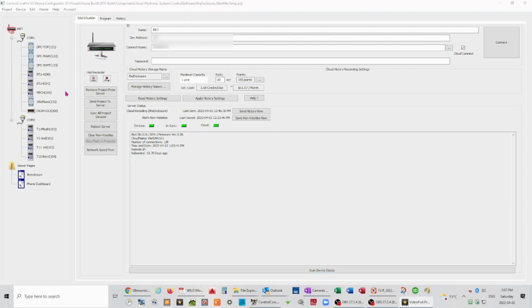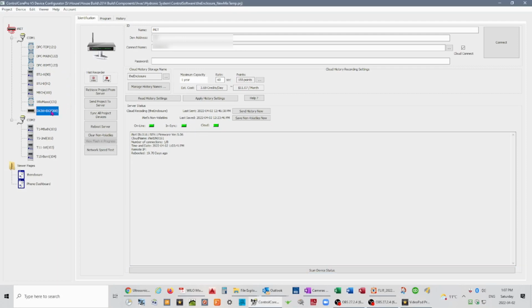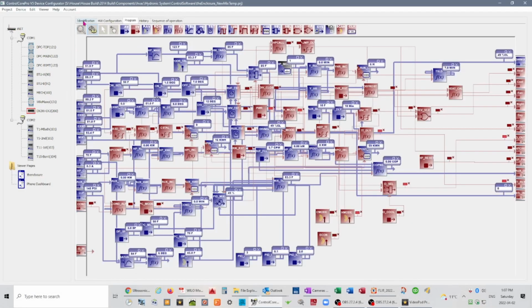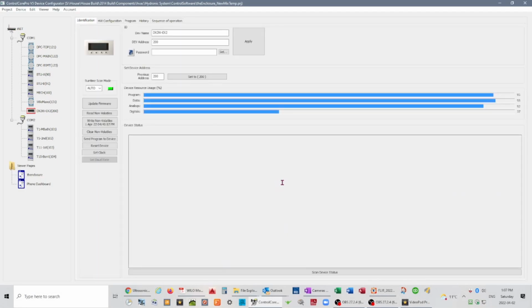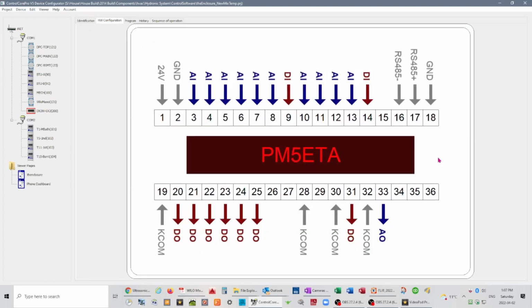Let's get into the nitty-gritty. We'll go straight to the DX2W. You start off with, again, just a basic screen where you're setting its device address. Each device on a Modbus network has to have a unique address, and this is similar to an IP address. The configuration page shows that PM5 ETA device, all of its available terminations, and then what each one does.